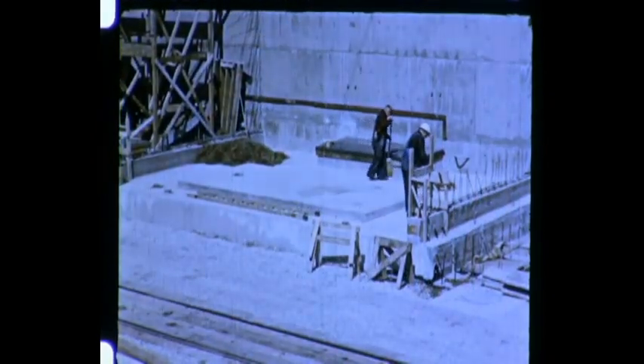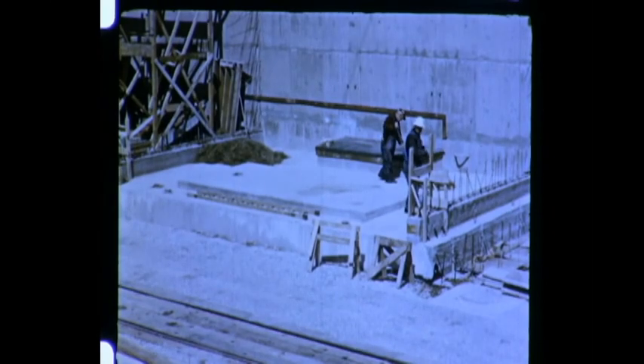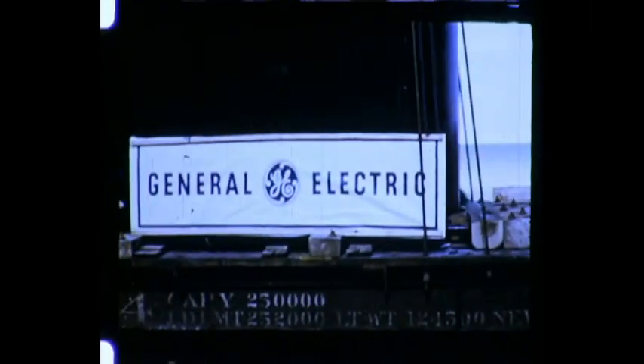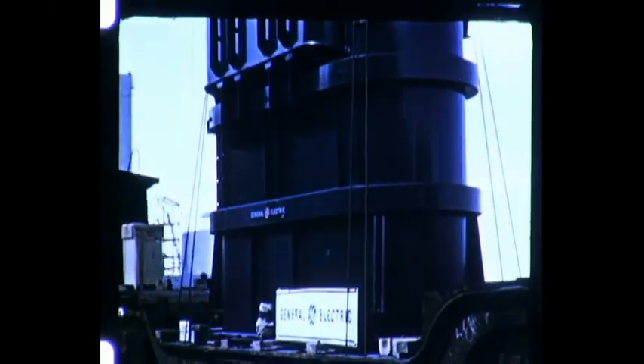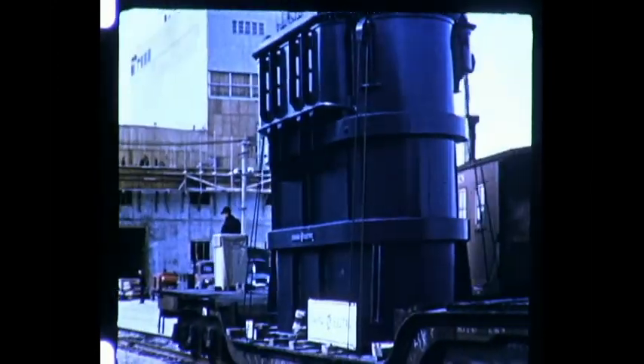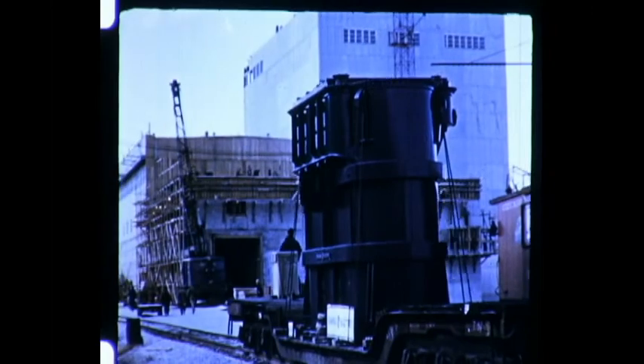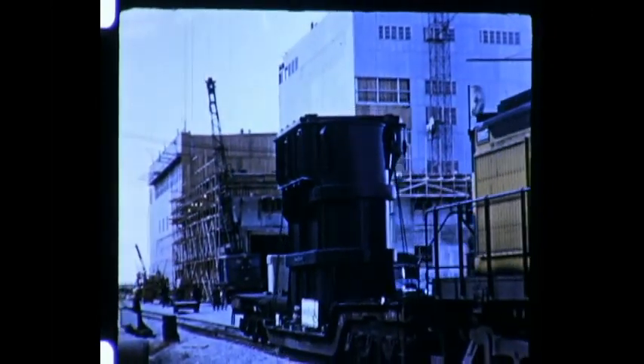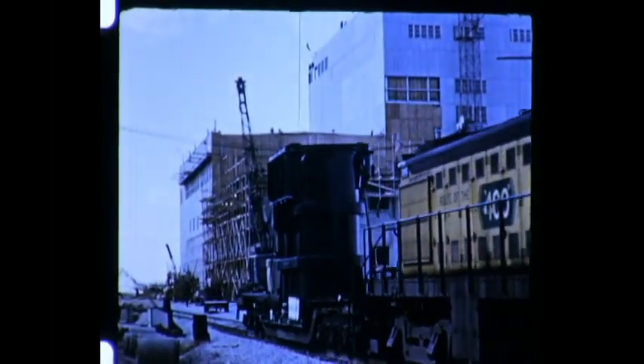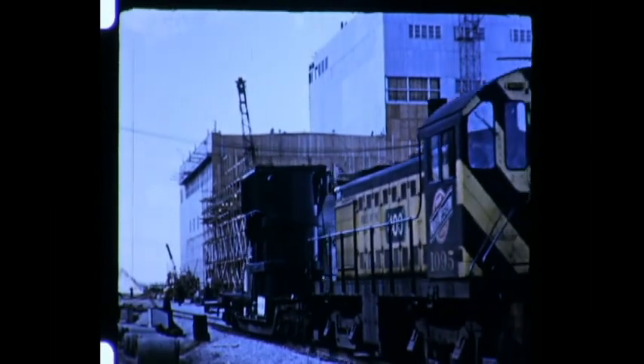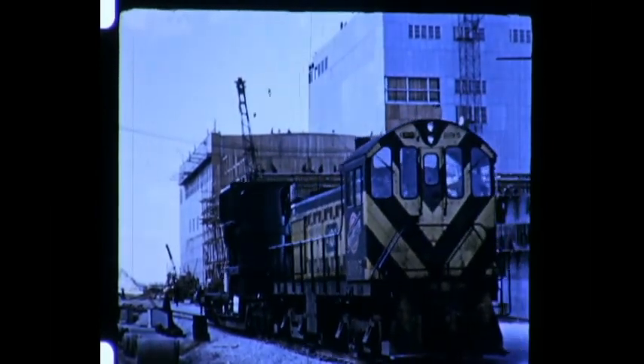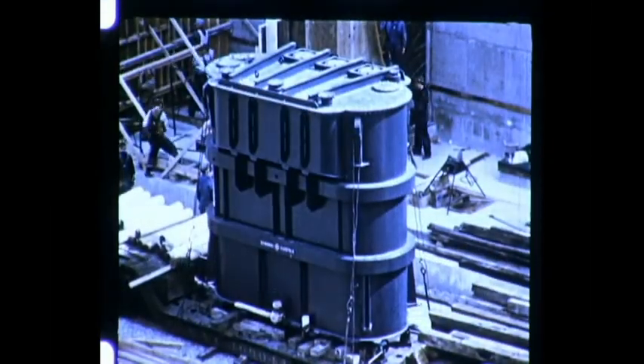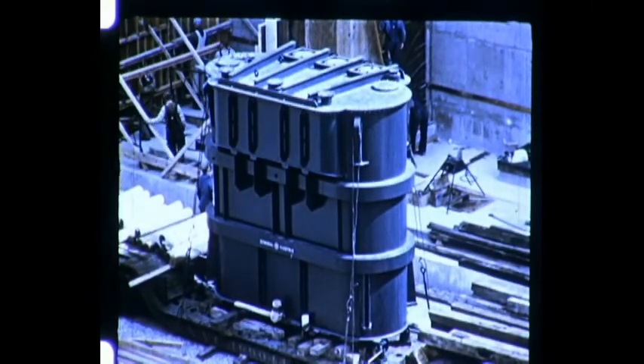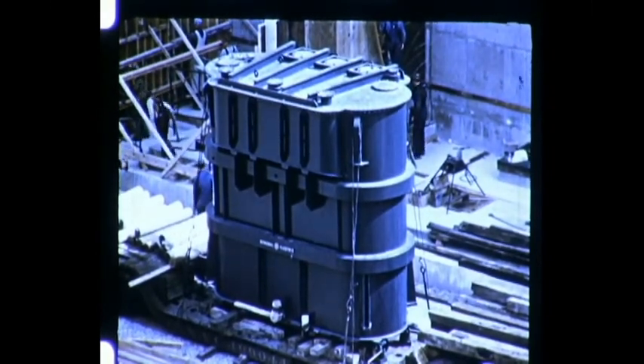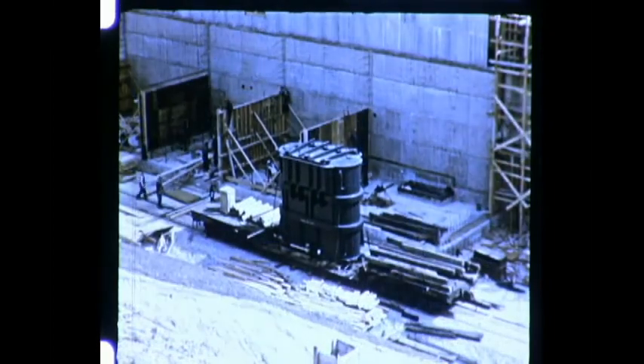At Oak Creek, solid concrete pads outside the turbine room will accommodate the transformers. Coming in on the siding is a General Electric forced oil water-cooled transformer rated 145,000 kVA. It should be remembered, of course, that installation methods may vary somewhat from those used here and at Delta Station. But in every case, handling of the units is made easier because they have been shipped upright in a one-piece tank. Let's look at some of the highlights.